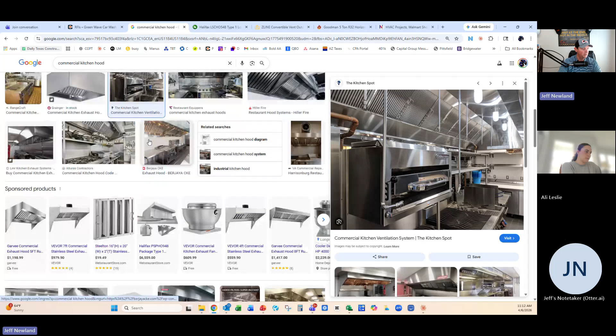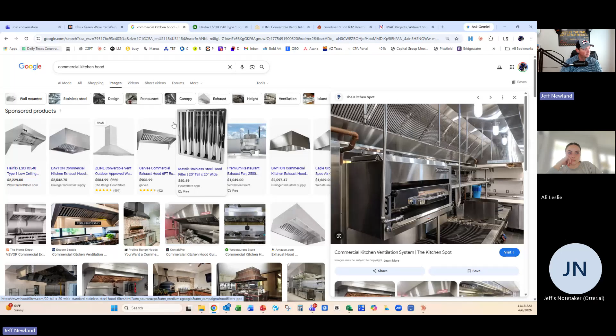That's why we try to get all the cut sheets to begin with, because a lot of times we don't even have electrical drawings, but if we did, the voltages called out for individual pieces of equipment can be different. So we've got to head that off in the submittal process so we don't pipe it, plumb it, and run electrical for a 110 circuit, but the equipment comes in with a big 220 plug and we've got nowhere to plug it in. Now we have to repull wire, change the plugs out, do a change order.